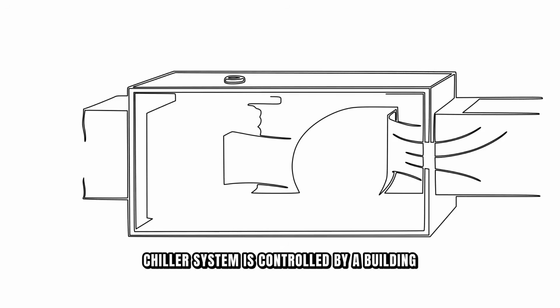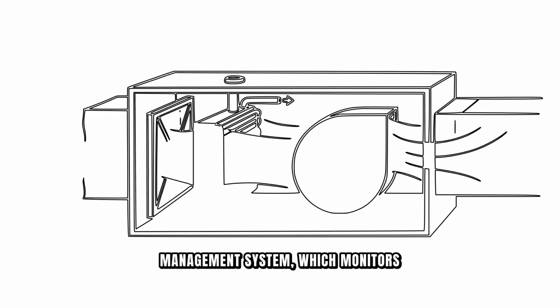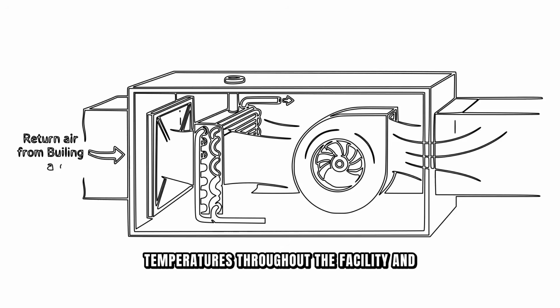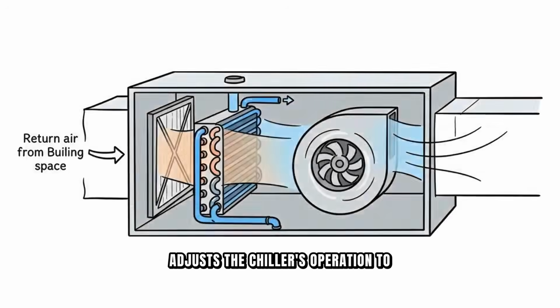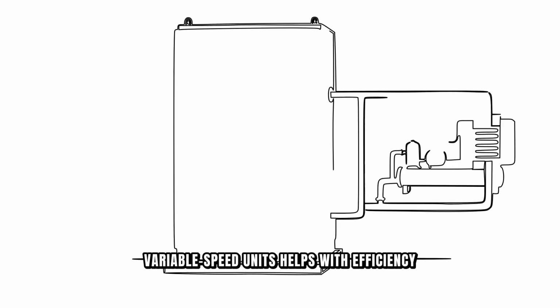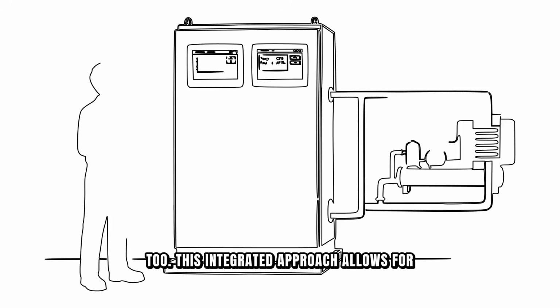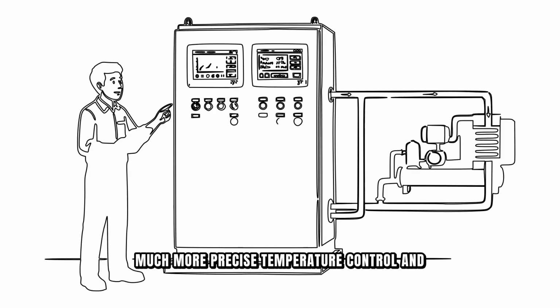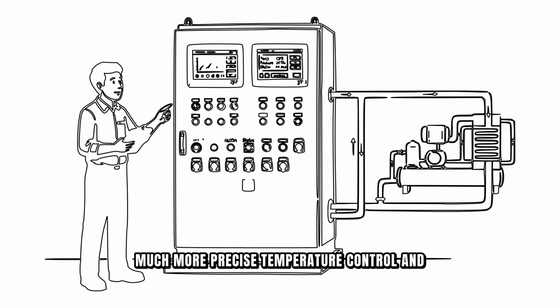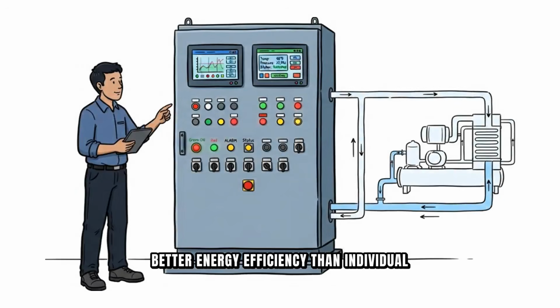The chiller system is controlled by a building management system, which monitors temperatures throughout the facility and adjusts the chiller's operation to maintain set point temperatures. Smart controls allow the system to operate efficiently by turning equipment on and off as needed. Adjusting compressor speeds in variable speed units helps with efficiency too. This integrated approach allows for much more precise temperature control and better energy efficiency than individual unit systems.